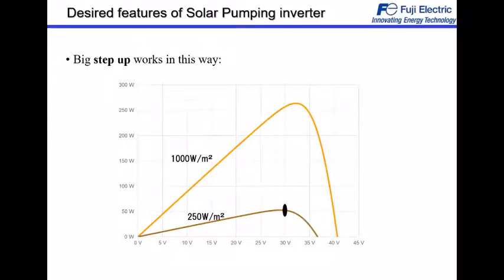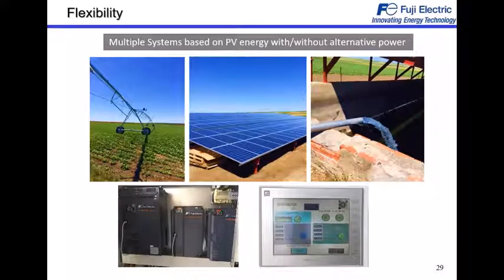Step up is the opposite. A cloud is there, and then suddenly there is much higher irradiation. What may happen is that the system becomes unstable. So the drive has a function to recognize this sudden change in irradiation and power, and searches for a point in a stable way, and then, with the MPPT, finds the maximum power point and stays there.